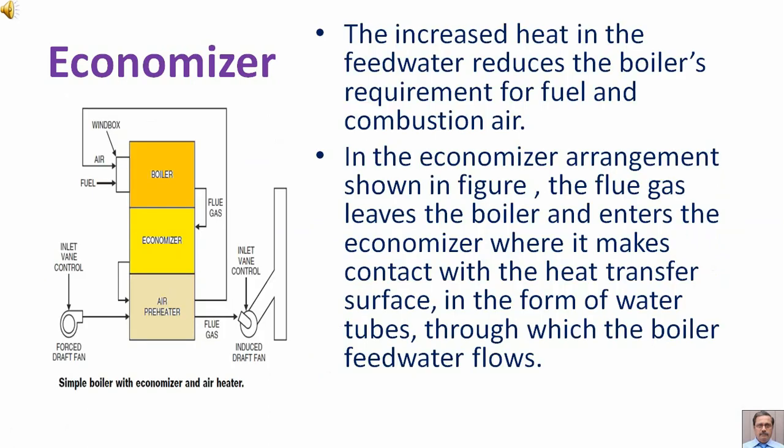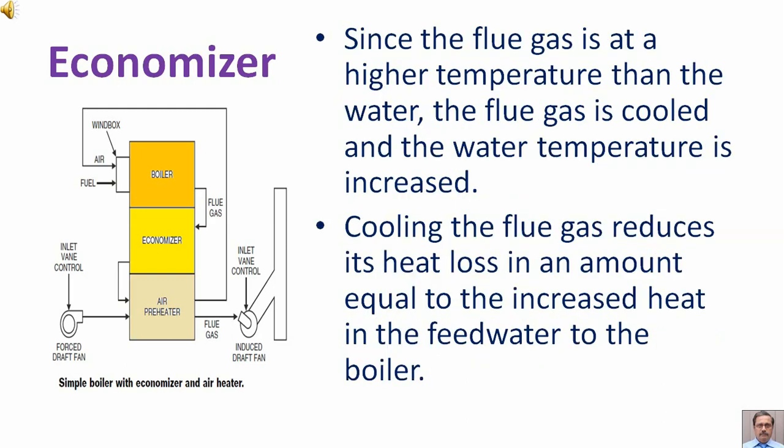Increased heat in feed water reduces the boiler's requirement for fuel and combustion air. In the economizer arrangement shown in the figure, the flue gas leaves the boiler and enters the economizer, where it makes contact with the heat transfer surface in the form of water tubes through which the boiler feed water flows. Since the flue gas is at a higher temperature than the water, the flue gas is cooled and the water temperature is increased. Cooling the flue gas reduces its heat loss by an amount equal to the increased heat in the feed water to the boiler.